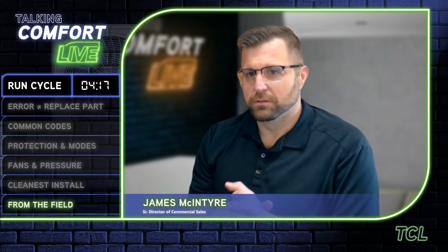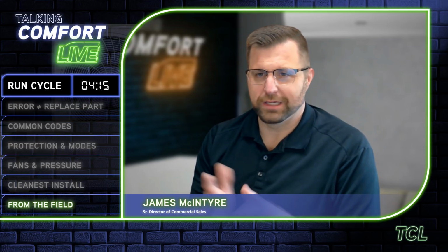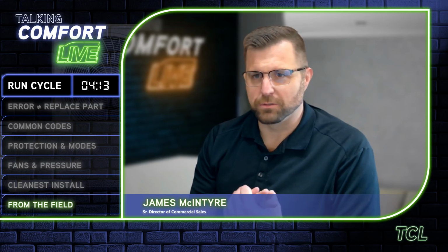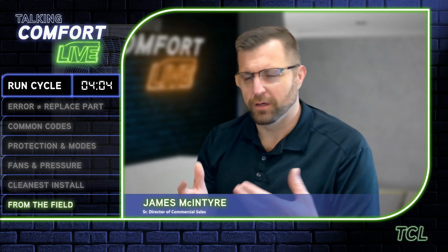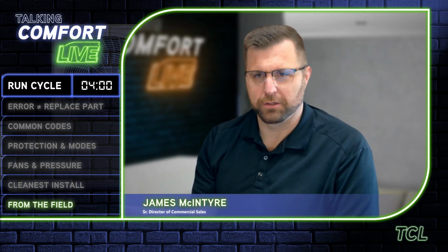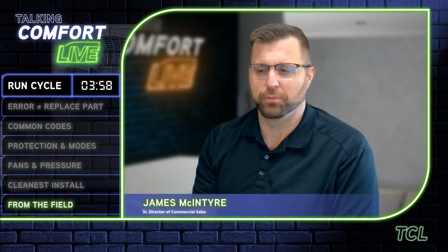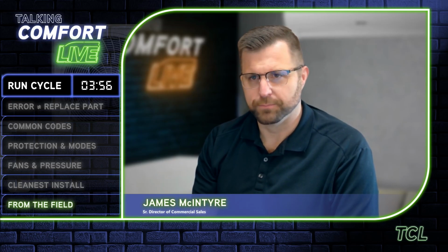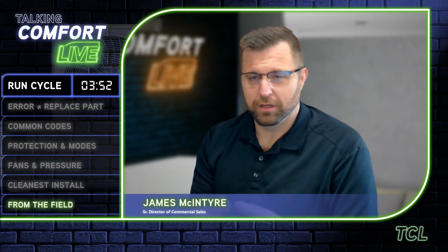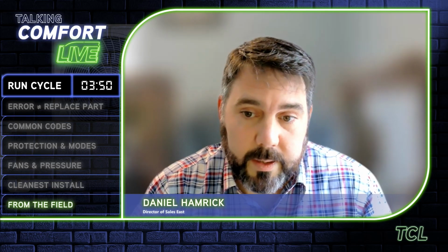And for nearly 20 years, I keep hearing people say you can't oversize inverter-driven systems. You absolutely can. There's minimum run times, there's minimum speeds, there's all kinds of built-in minimums to protect themselves and all that. You can still oversize them and have them run incorrectly, taking away their ability to properly dehumidify. And it's more common than you might think.